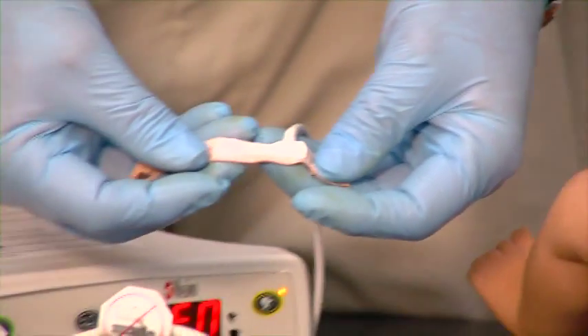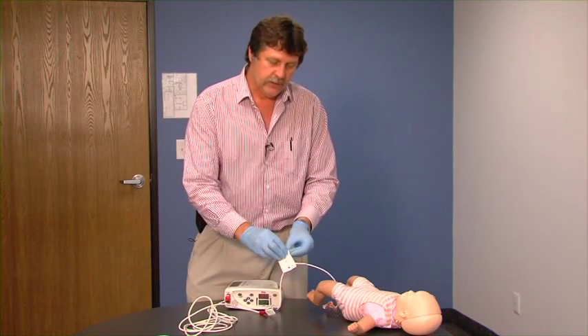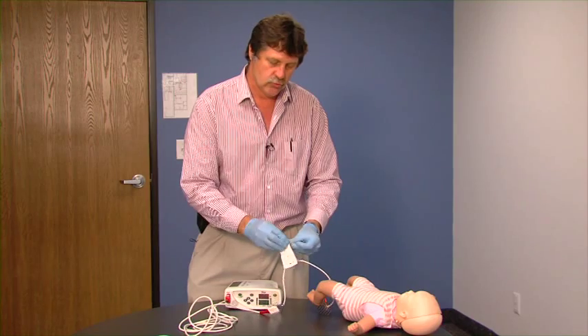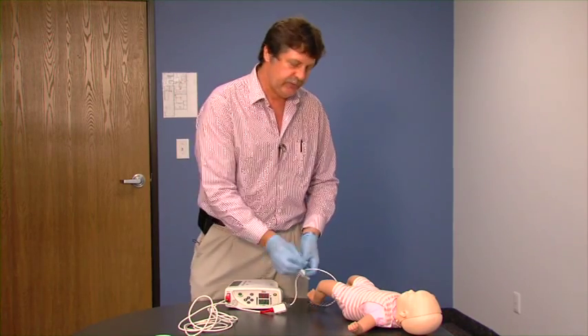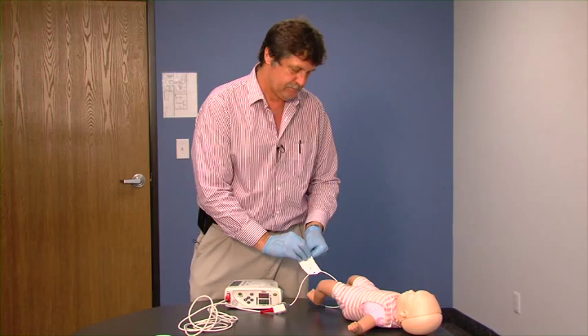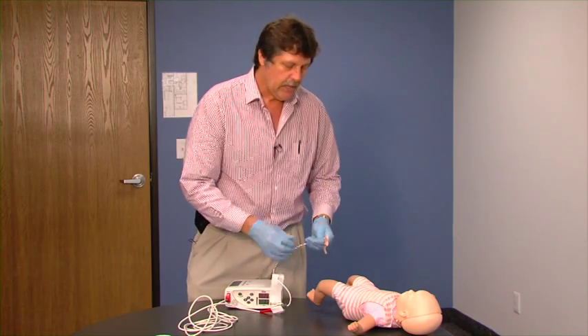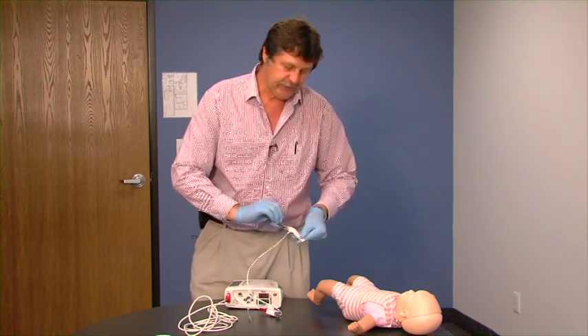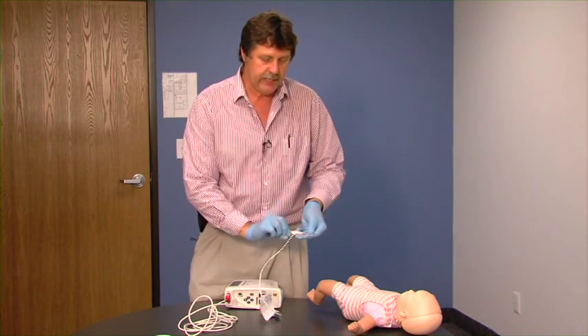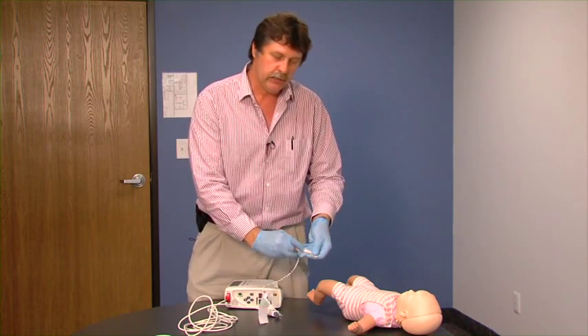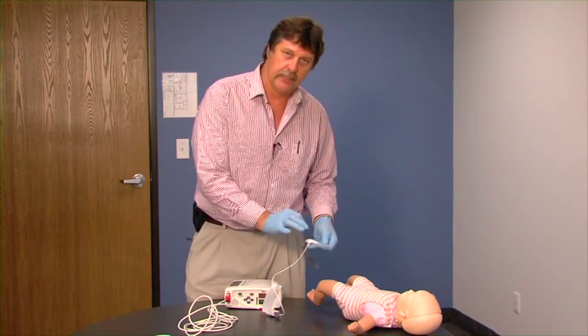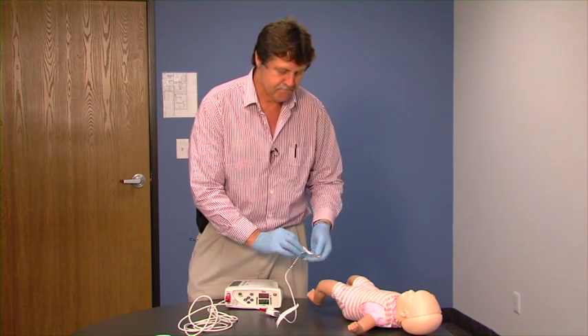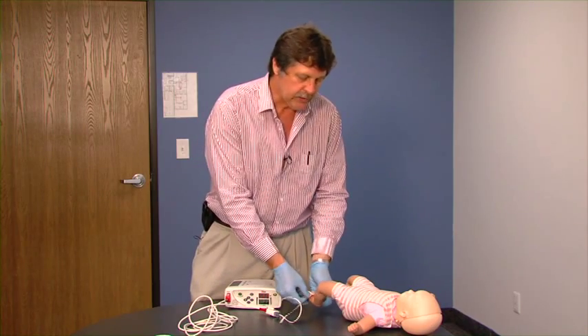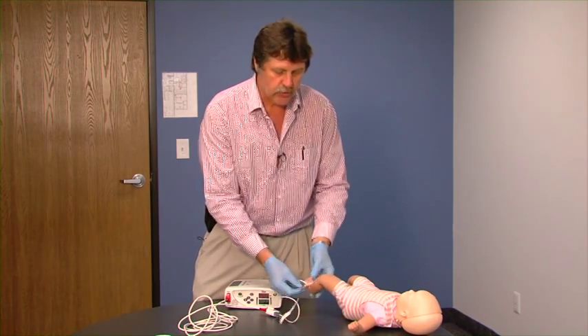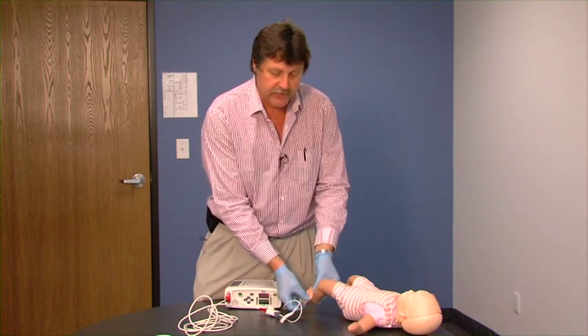Okay? If it loses its adhesiveness, we can peel off one of these little adhesive dots and use this to adhere it to the patient's foot. Now also on a daily basis, we want to remove this and take some isopropyl alcohol and clean the surface of the sensor. Make sure that we're getting a good contact. Okay. On a weekly basis, we're going to remove the adhesive wrap and replace that altogether.